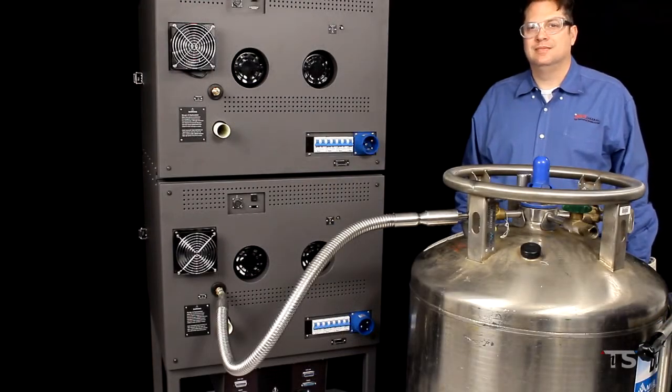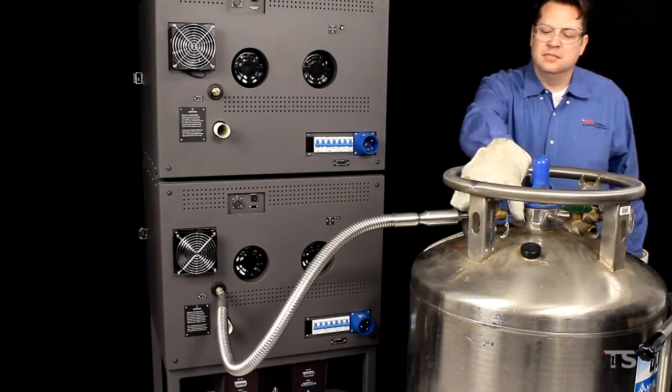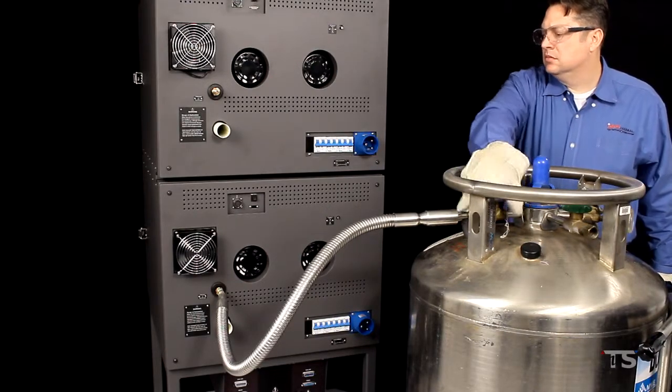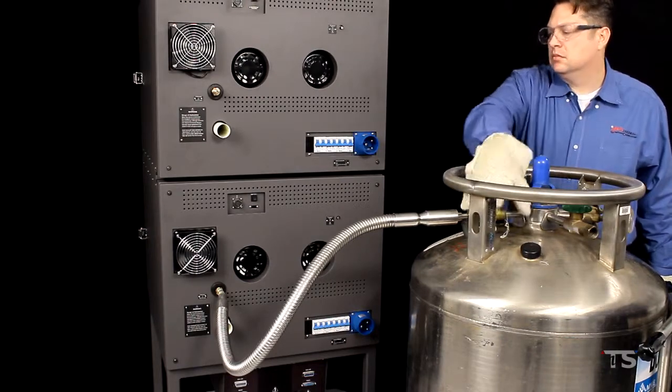Now that your wrenches are adjusted to fit the cryo inlet connections, open the blue valve on the Dewar. Liquid nitrogen will begin flowing from the Dewar to your thermal chamber.